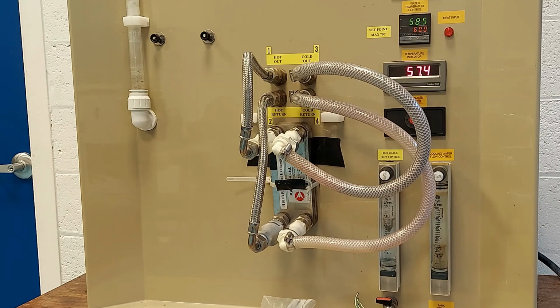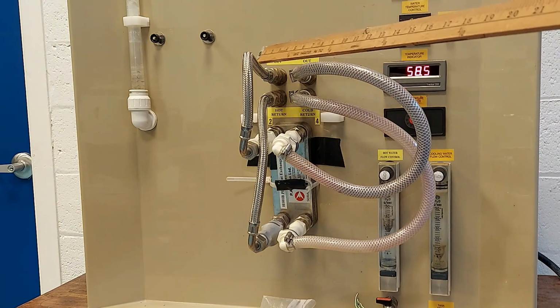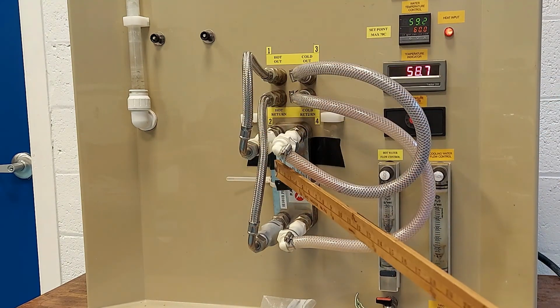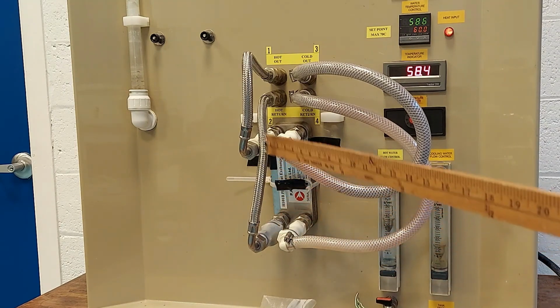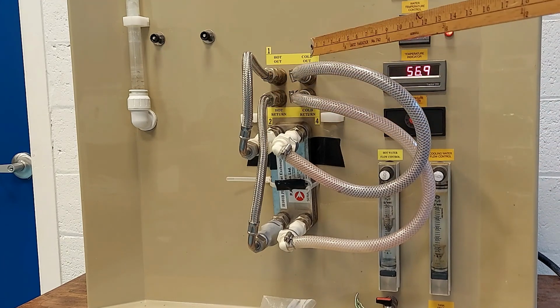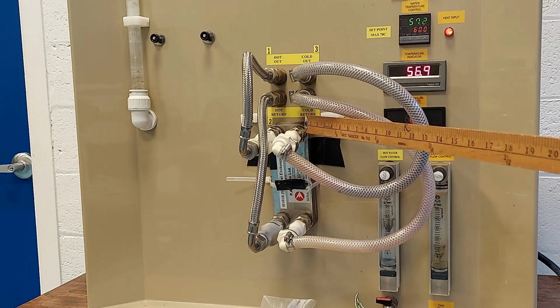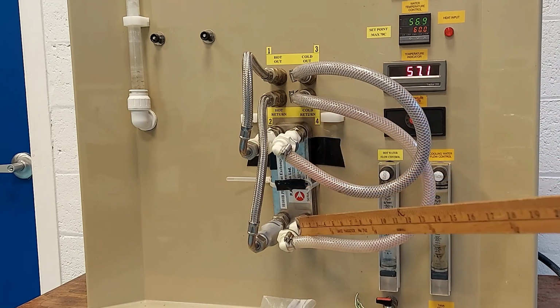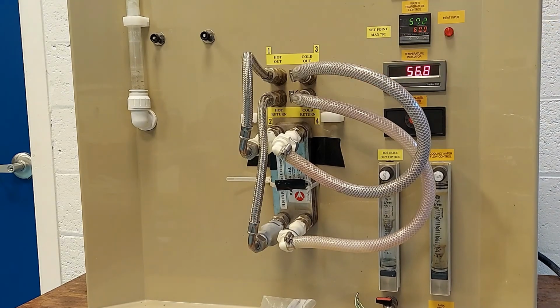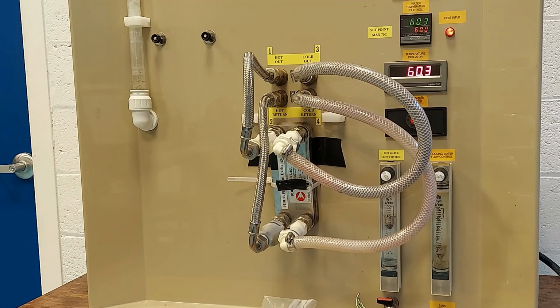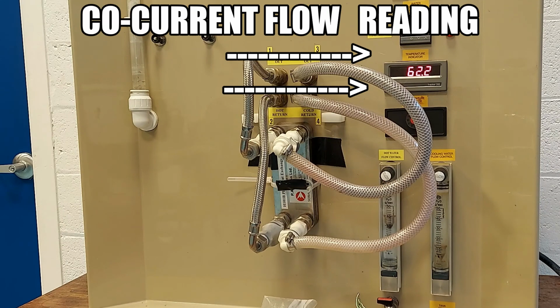At this point, the machine is configured for co-current flow, where we have the hot water going into the heat exchanger and coming down and exiting on the return line to the system. We have the cold water going into the plate heat exchanger, coming down and exiting to the sink. Now we are observing our actual water temperature, which is now 59, and our preset temperature is 60. So at this point we will observe equilibrium. At this point we are at equilibrium, so we can begin our first readings.